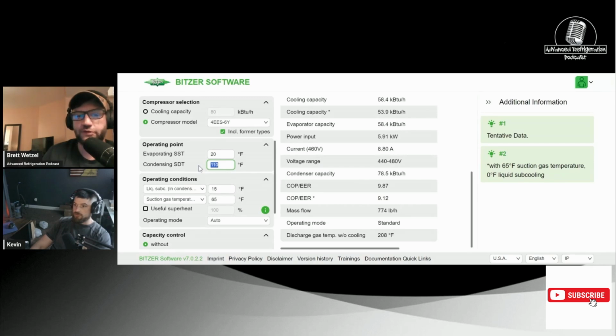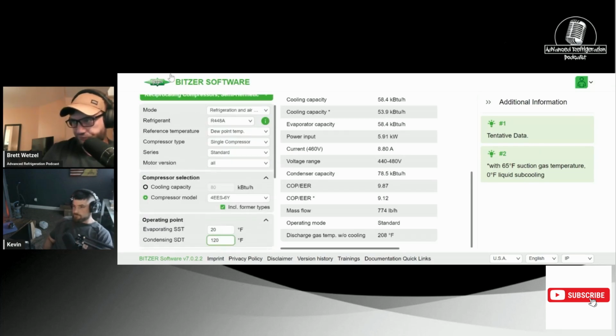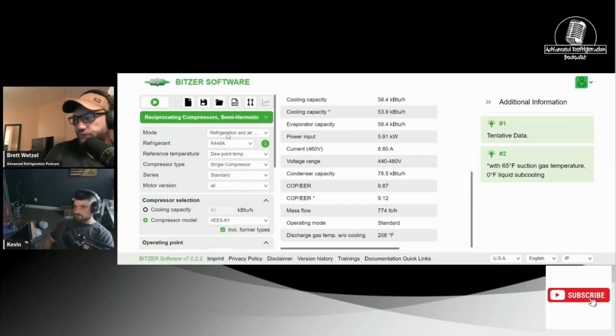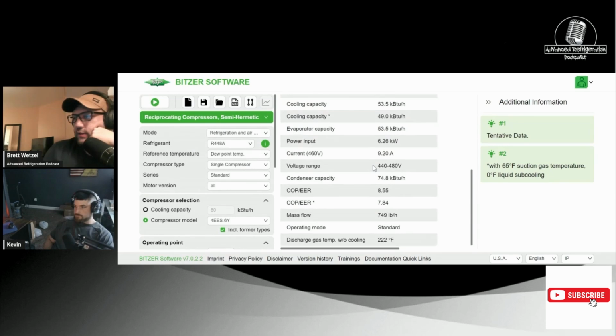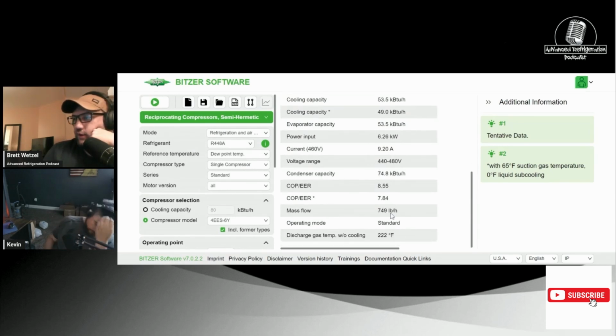So let's increase. Let's just say instead of Chicago, we're running here in Texas where it's really hot. So we'll run it at 100. Should I just do 120? Because 125 is usually where they have the high pressure switches set for, or the EMS. So 120. We'll go back up to the play button, and we were at 8.8. And now we are running an amperage of 9.2. So you see how we went up, guys, and it was just slightly.